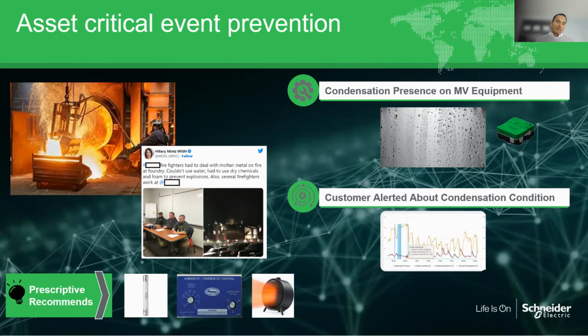But call it global warming, call it climate change, however you want to call it — for a few years now, humidity levels have been on the rise. So now humidity levels and temperature swings at different times of the year are creating a problem. We got to the root cause of this issue not only through technology, but also through understanding how this piece of equipment was put together — that human consultation, the human interaction with the customer. Now the customer, understanding the problem, is able to issue a work order and purchase orders to fix the problem at the root, where it really started. So again, this is a case where we were able to prevent a third critical failure that was about to happen.